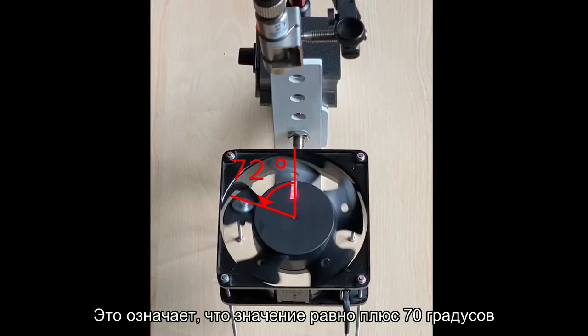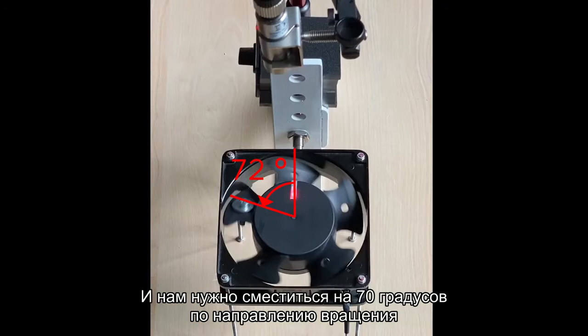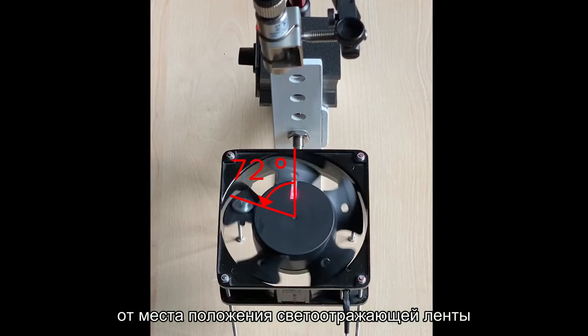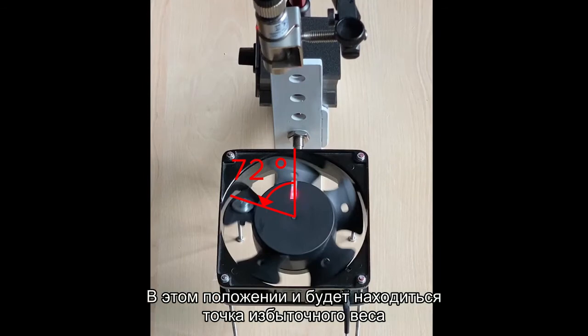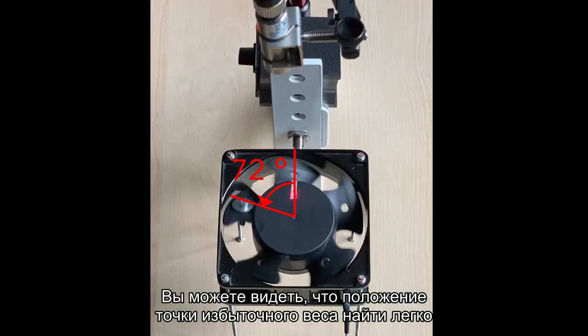It means the value is plus 70 degrees. And we have to go 70 degrees forward in the rotation direction from the reflective tape position. In this position is the heavy spot. You can see that it is easy to find the heavy spot position.